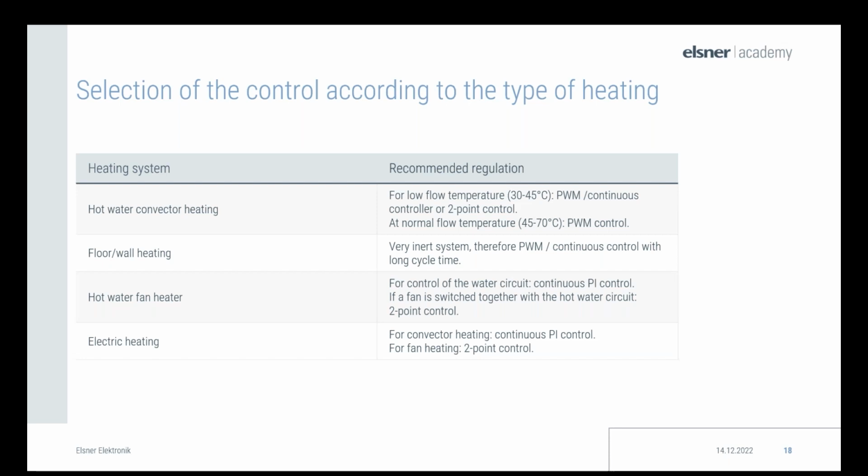controller, or 2-point control. At a normal flow temperature, 45 to 70 degrees, a pulse width modulation control is required. If you do not know what the pulse width modulation means, we will discuss this in the following slide. So I'm just asking for a little bit of patience.